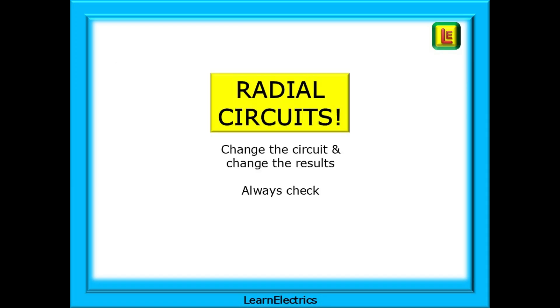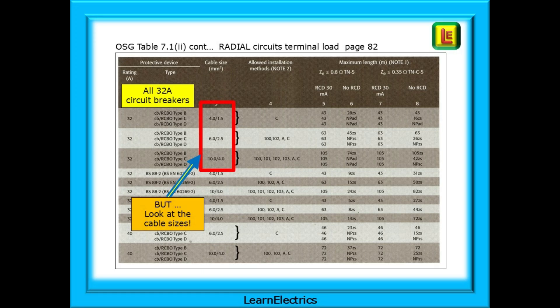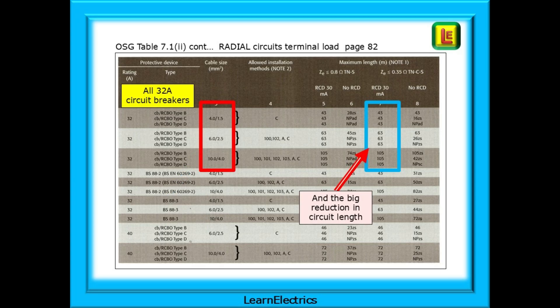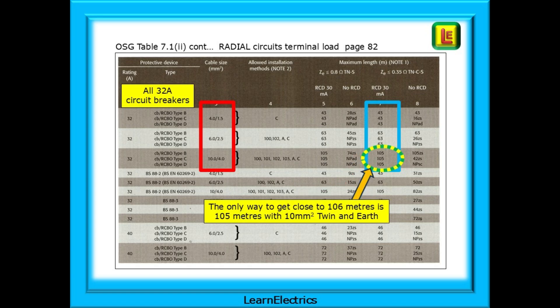A heads up about radial circuits - if you change the circuit, you will change the results, so always check. This is the same Table 7.1.2, but page 82, showing radial circuits with a terminal load - in other words, all the load is at the furthest end of the circuit. Think of a shower or cooker circuit; it's all at the end - a terminal load. The red box shows 32 amp breakers again, but now look at the cable sizes: 4, 6, and 10 square millimetres, and look at the big reduction in circuit length. For the radial circuits shown, the only way to get close to 106 metres is 105 metres with 10 square millimetre twin and earth. Ring and radial circuits must be treated differently, and we should always check before simply splitting a ring into two radials - sometimes it won't work safely.